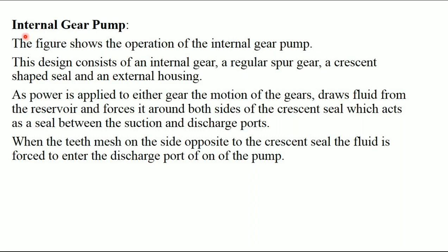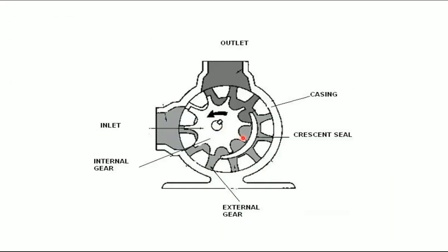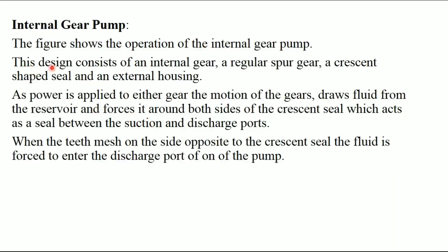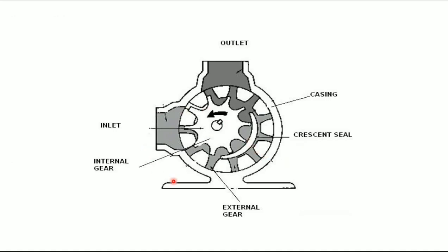Next, we will see the internal gear pump, which comes under the positive displacement pump category. This is the diagram of the internal gear pump. This design consists of an internal gear, a regular spur gear, a crescent-shaped seal, and an external housing. As power is applied to either gear, the motion of the gears draws fluid from the reservoir and forces it around both sides of the crescent seal, which acts as a seal between suction and discharge ports. When the teeth mesh on the side opposite to the crescent seal, the fluid is forced into the discharge port of the pump. This is the construction and working of the internal gear pump.